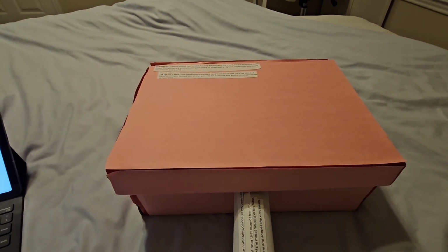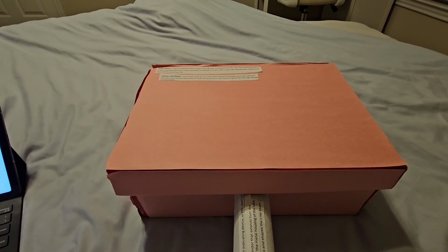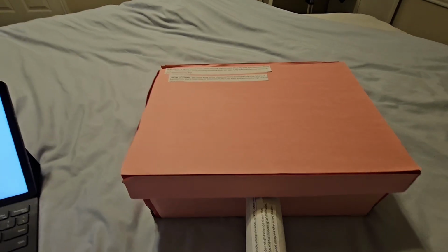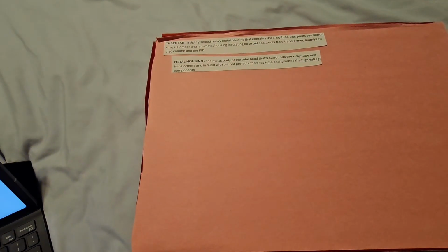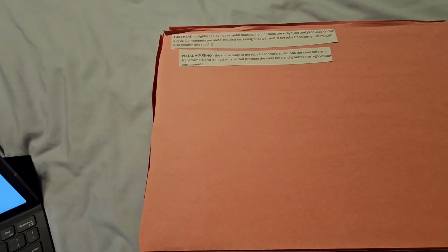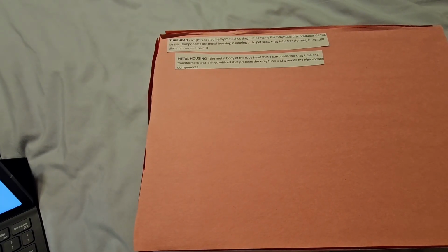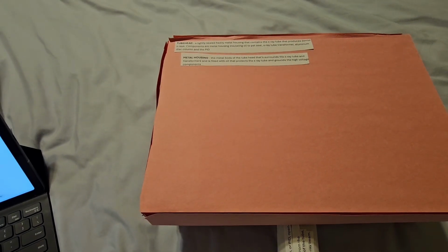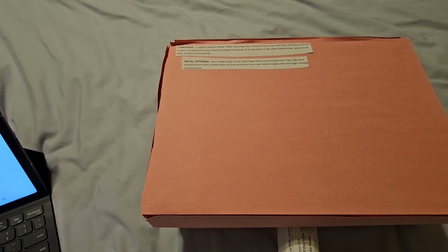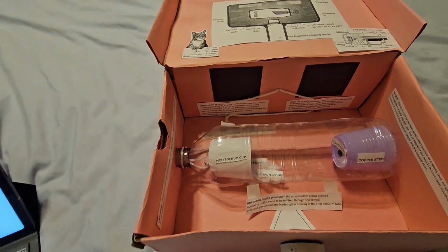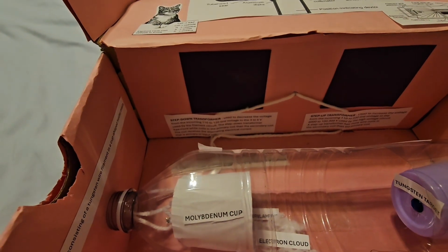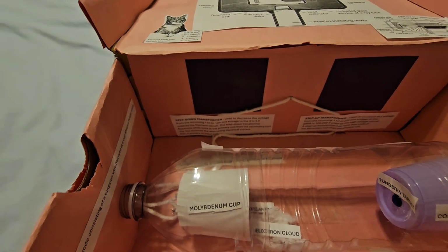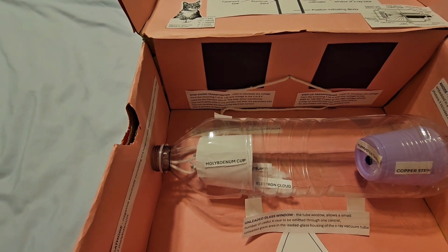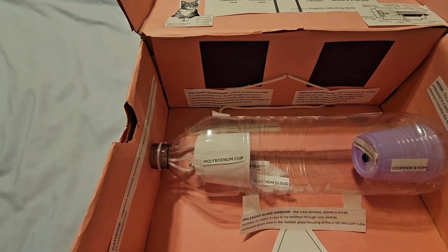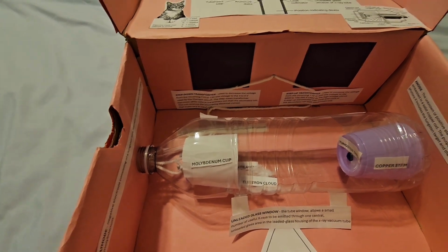There are three main components of a dental X-ray machine: the control panel, the extension arm, and the tube head. The tube head is a tightly sealed heavy metal housing that contains the X-ray tube which produces the dental X-rays. The body of the tube head is made of a metal housing that surrounds the X-ray tube and transformers. The transformers are used to increase and decrease voltage, and the entire housing is filled with an insulating oil. This oil prevents overheating by absorbing the heat produced by X-ray generation.